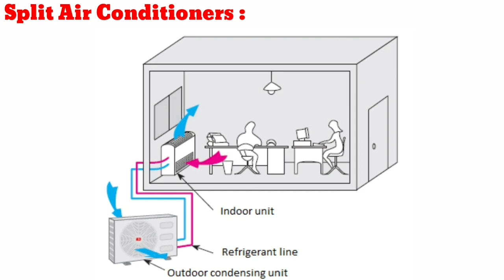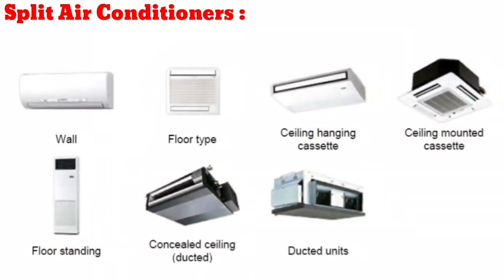The outdoor unit is usually pre-charged with refrigerant during manufacture. The majority of models currently being sold are reversible — they can operate as an air conditioning unit in hot weather or provide heating as an air-to-air heat pump in cold weather. In heating mode, the indoor unit functions as condenser and the outdoor unit as evaporator. Indoor units can be ducted or non-ducted. Non-ducted indoor units can be wall mounted, floor mounted, cassette ceiling suspended, built-in horizontal, built-in vertical, or mobile. Ducted indoor units can deliver cool air to several rooms or to several spots within a single room, distributing cool air evenly — mostly used in hotels or large apartments.